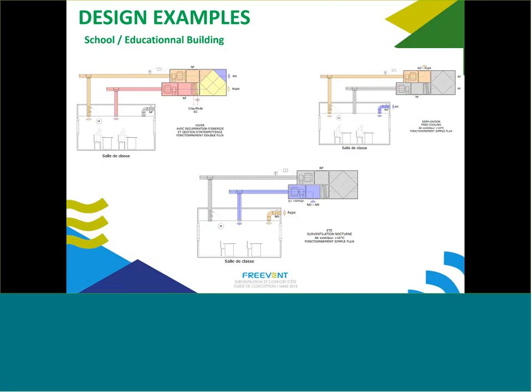Three degrees is a good threshold to start ventilative cooling. School and educational buildings are really good for ventilative cooling because the ventilation flow rate needed during the day for occupancy is already quite high — these are rooms with a lot of occupancy. So at night, sometimes you don't need to add much to have the airflow needed for ventilative cooling. Sometimes you just have to run the fan at night and it's done. A good rule is to try to have only one fan working instead of the balanced fan, dividing the electrical consumption by two.